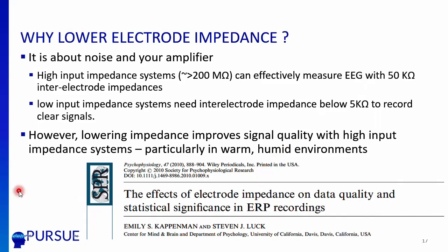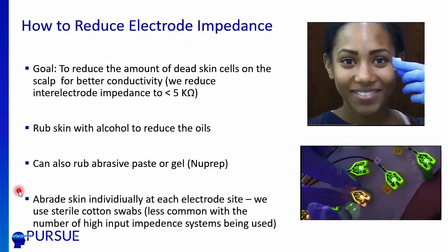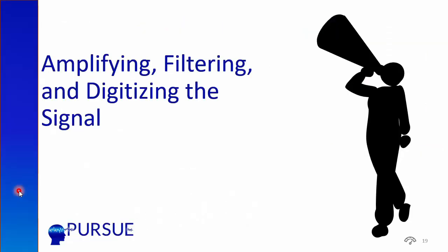How do you reduce electrode impedance? We want to remove the oil and dead skin cells to get below 5 kilohms. One thing you can do is rub or clean the skin with alcohol — we do this for our ocular electrode sites and reference electrode sites, since it's faster and easier. You can remove makeup, oil, and dead skin cells to lower electrode impedance. Then we individually abrade the skin: we take a sterile cotton swab, stick it through the hole, and gently rub on the person's skin to lower impedance.